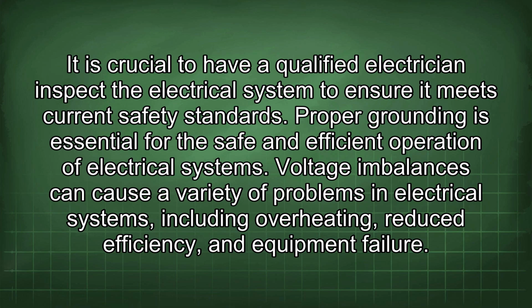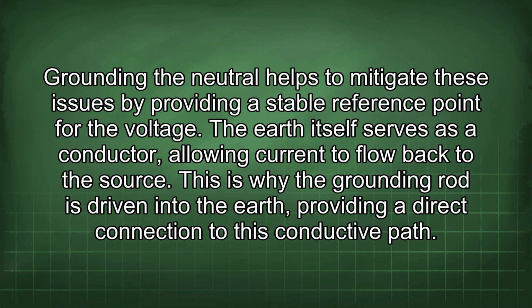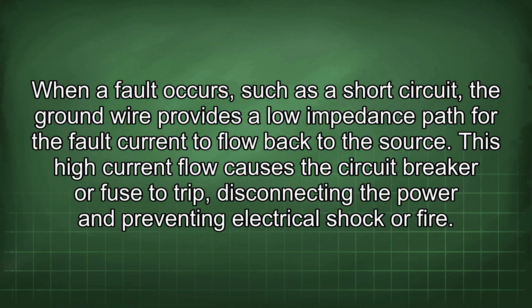Voltage imbalances can cause a variety of problems in electrical systems, including overheating, reduced efficiency, and equipment failure. Grounding the neutral helps to mitigate these issues by providing a stable reference point for the voltage. The earth itself serves as a conductor, allowing current to flow back to the source. This is why the grounding rod is driven into the earth, providing a direct connection to this conductive path. When a fault occurs, such as a short circuit, the ground wire provides a low impedance path for the fault current to flow back to the source.